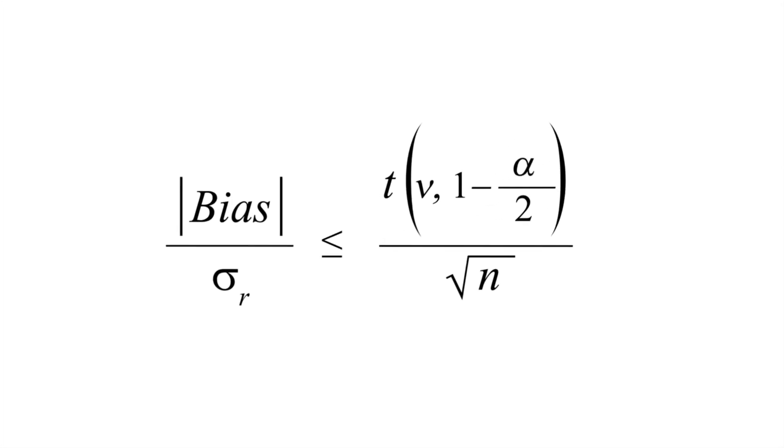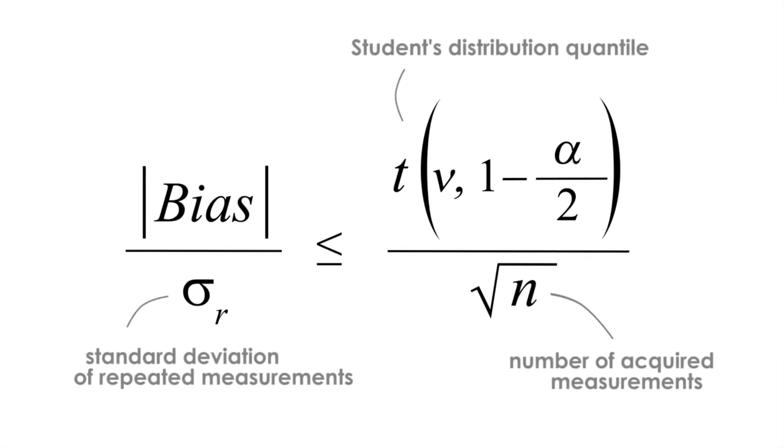The left side of the formula compares the bias to the repeatability through dividing the average bias by the standard deviation of the repeated measurements. This fraction must be equal or less than the criteria given on the right side.